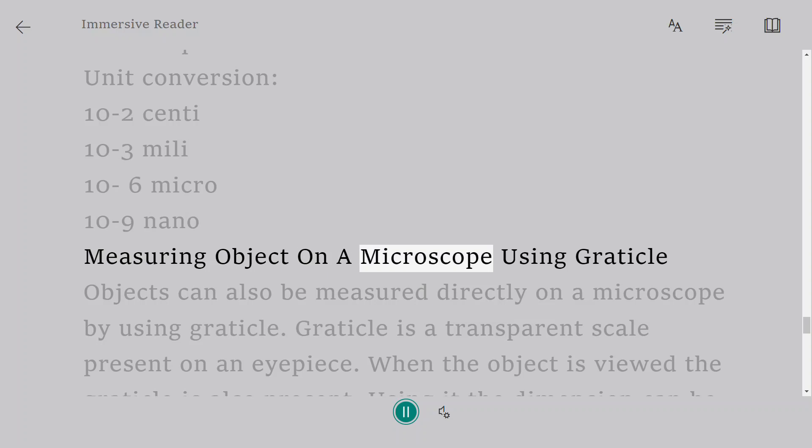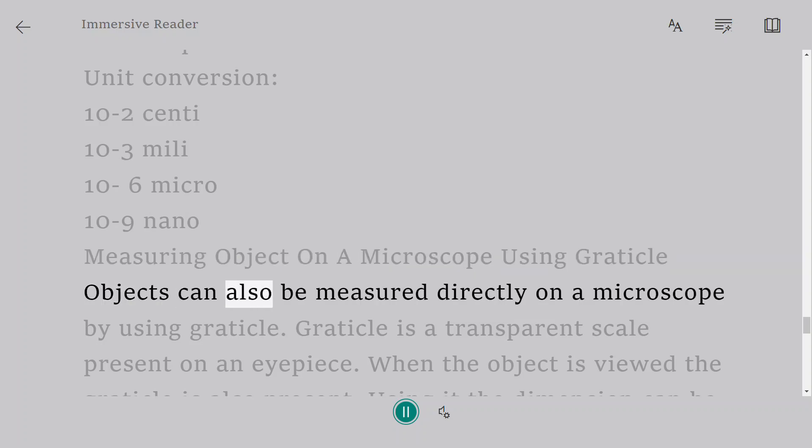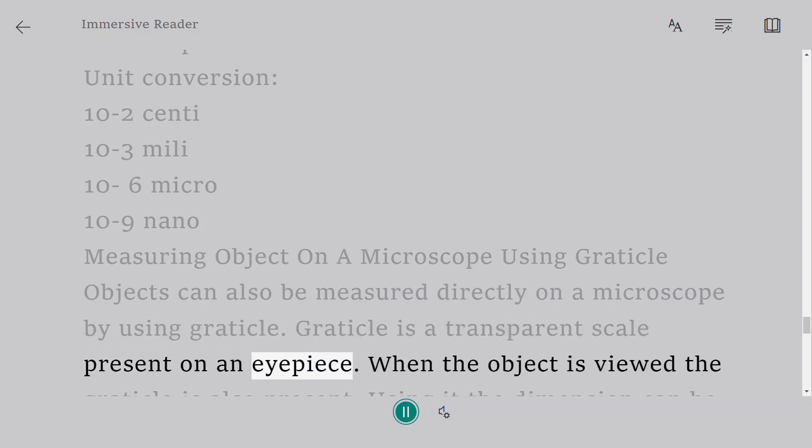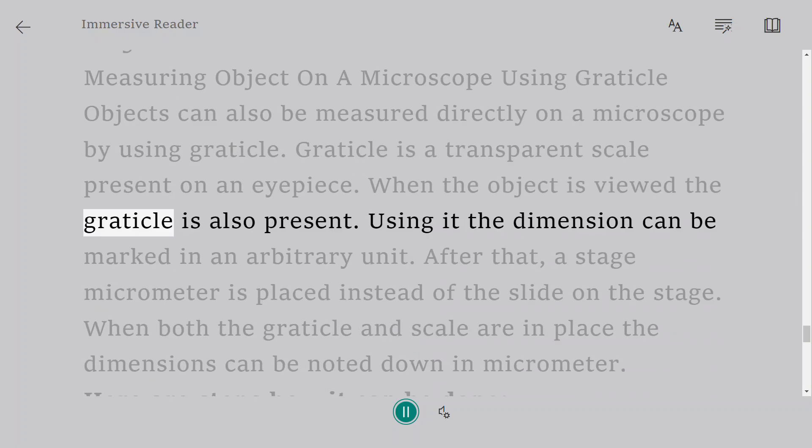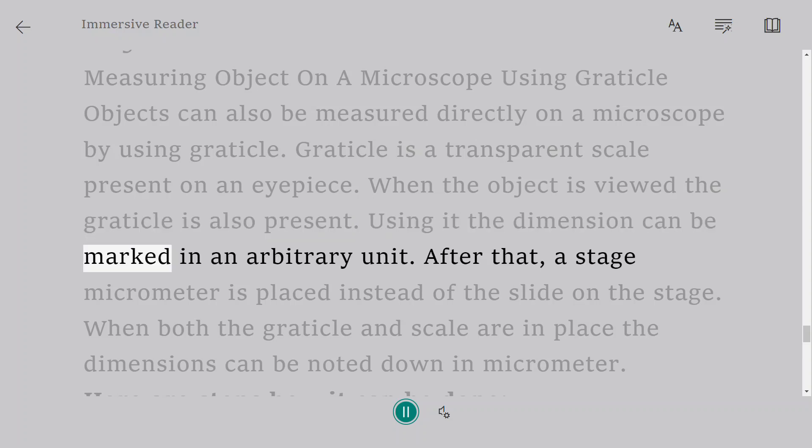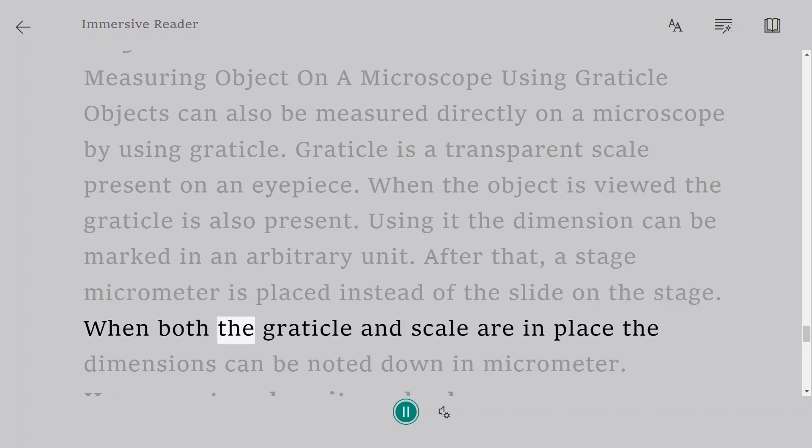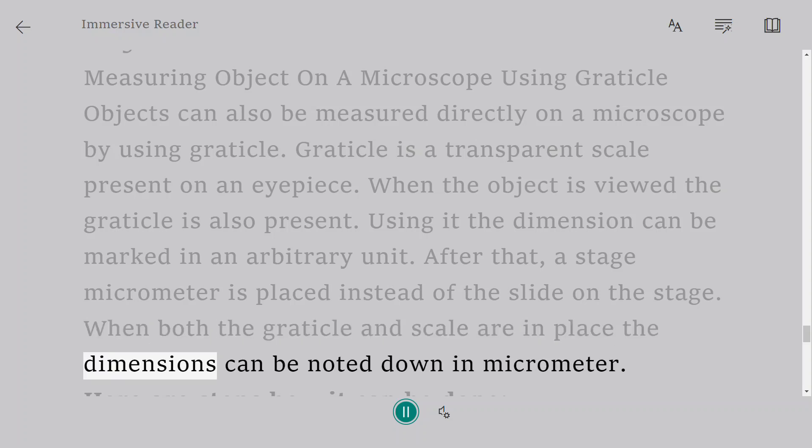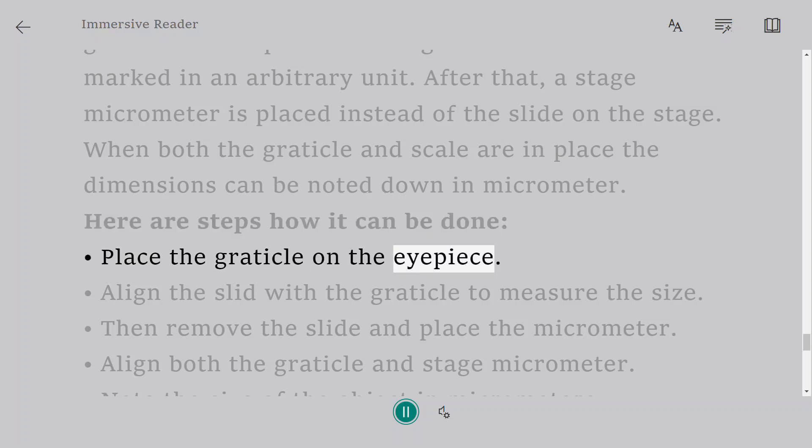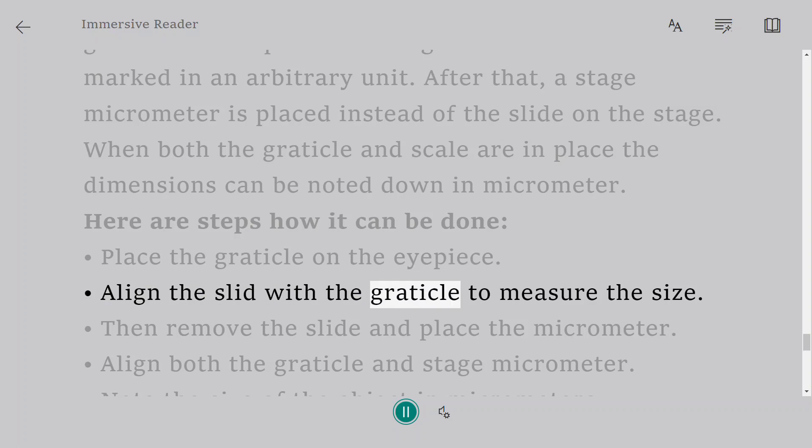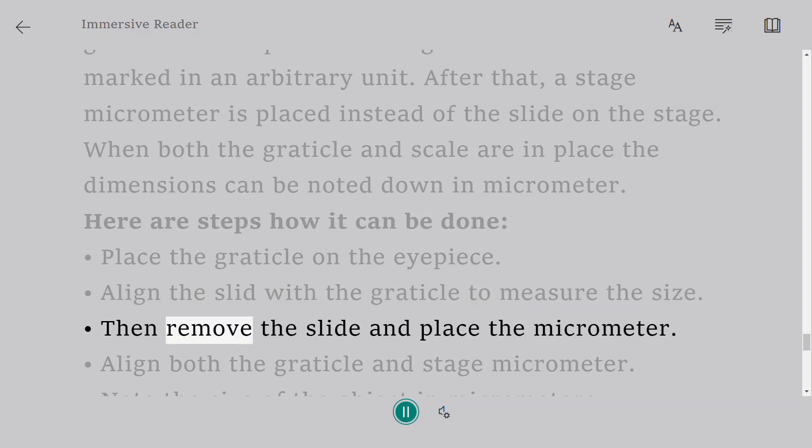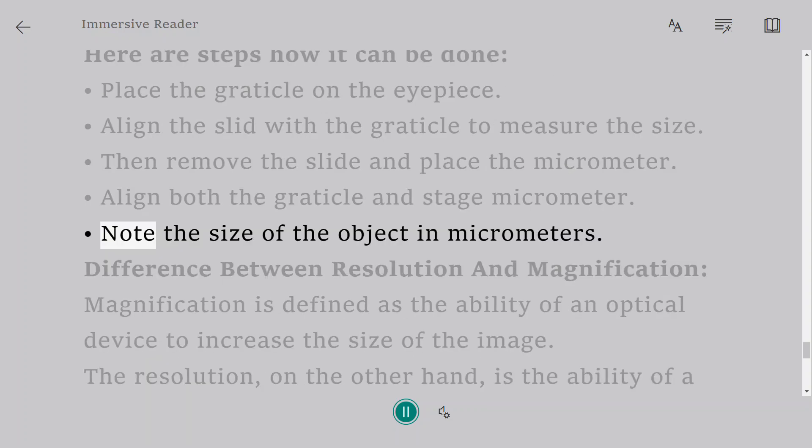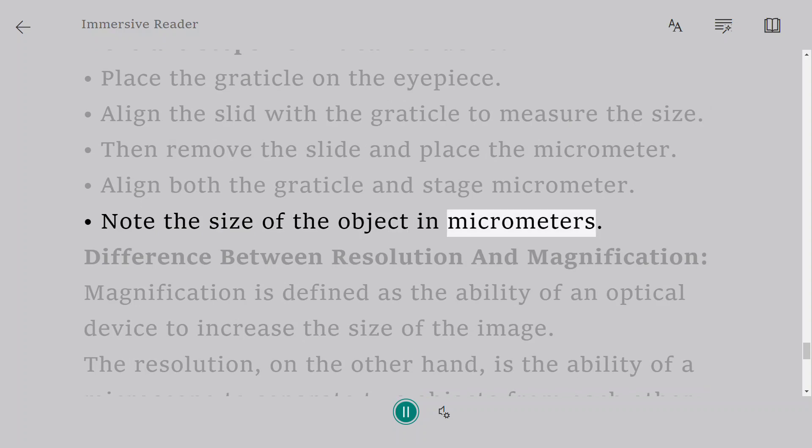Measuring object on a microscope using graticule. Objects can also be measured directly on a microscope by using graticule. Graticule is a transparent scale present on an eyepiece. When the object is viewed the graticule is also present. Using it the dimension can be marked in an arbitrary unit. After that, a stage micrometer is placed instead of the slide on the stage. When both the graticule and scale are in place the dimensions can be noted down in micrometer. Here are steps how it can be done. Place the graticule on the eyepiece. Align the slide with the graticule to measure the size. Then remove the slide and place the micrometer. Align both the graticule and stage micrometer. Note the size of the object in micrometers.